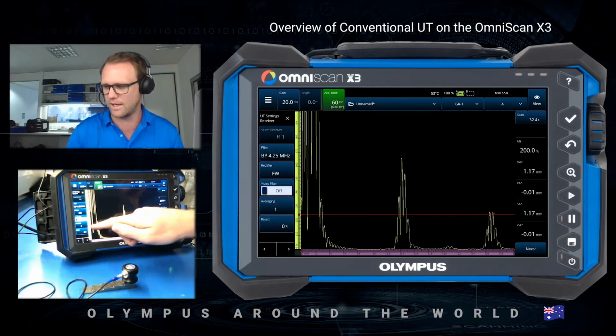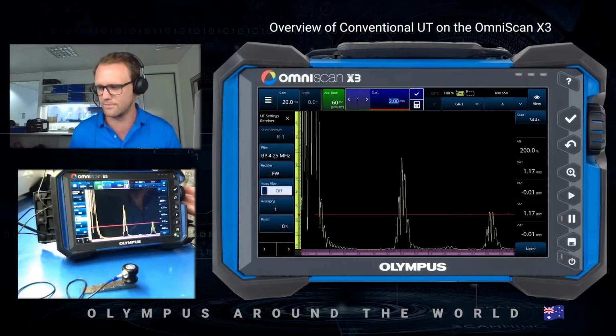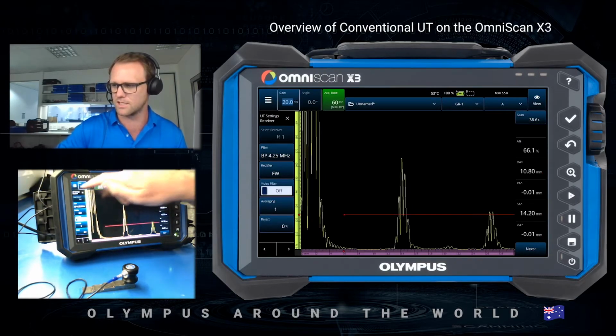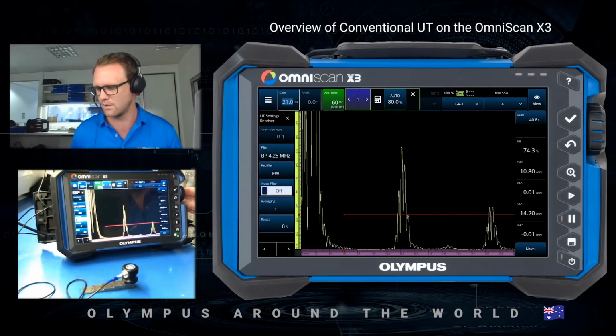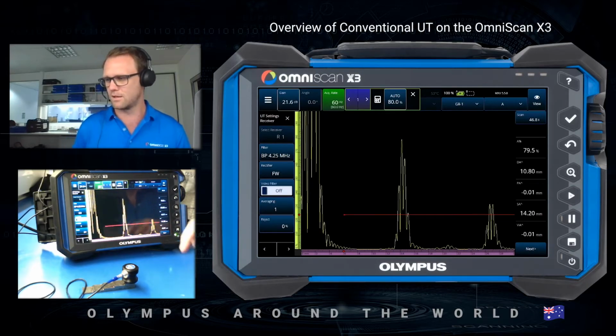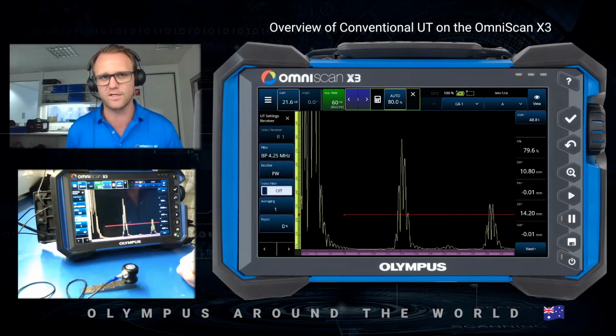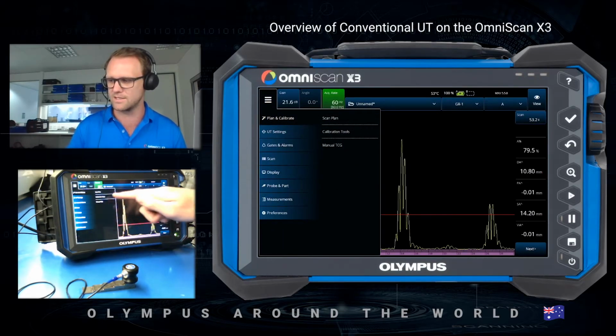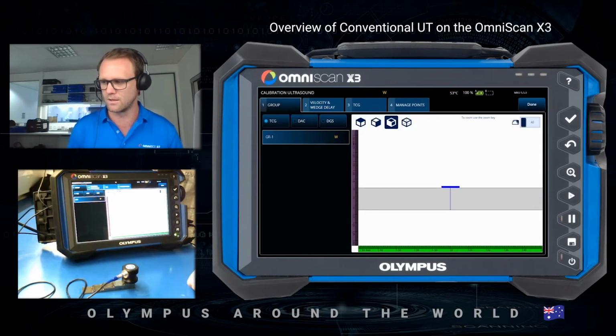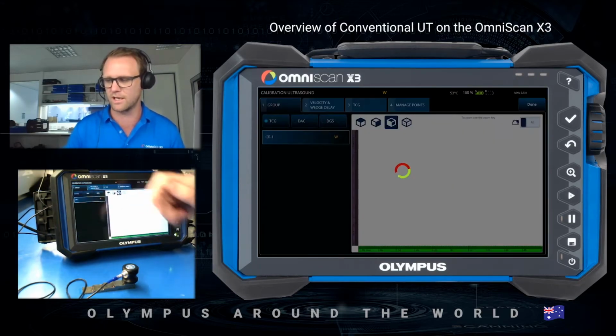Okay, so now I have a UT set that hasn't been calibrated, but I can move my gates, I can change my gain, and I have my measurements on the right side. If I wanted to auto 80 my gain, I just do it here. Okay, so the next step is to do the calibration using the software. So back into the burger menu and plan and calibrate, and this time I select calibration tools. Within this page, I can access the TCG, but I'm just going to do the velocity and wedge delay.